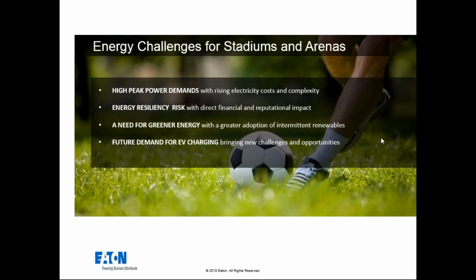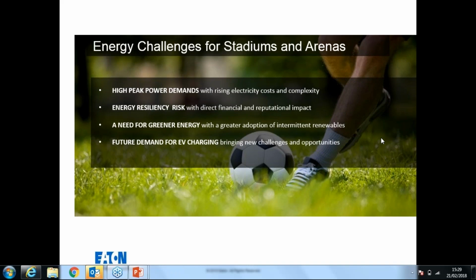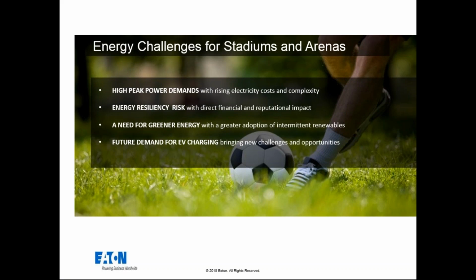Okay, thank you. So what are the energy challenges for stadiums and arenas? We think out of all of the building types that we work in, stadiums and arenas have the most unusual peak power demands. During major events, we can see the peak power demand surge as demand increases for lighting, TV broadcasting, and catering concessions. Typically in large stadiums, we can see power demands in the region of 5 to 7 times the normal base load. With it, this brings some real challenges. Firstly, in terms of the actual costs of supplying power, which is normally a combination of the amount of energy used, but also the capacity that power is being consumed at, so the power rating. Also the complexity of managing that peak and the risks it brings in terms of excess demand on the local grid, which can cause stability risks.